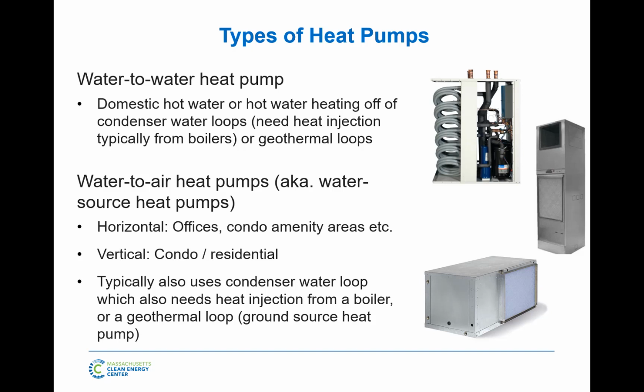Then there are the water-to-air heat pumps. That's what's commonly known as water source heat pumps. There are horizontal versions, common for office buildings and general areas, usually up in the ceiling. They go as small as a couple of tons. They can go pretty big. You can get a 10-ton water source heat pump, even larger sometimes. And then the vertical heat pumps, typically for condo buildings, maybe a third to half of the new build residential condo market, and especially mid-rise, high-rise, probably still use water source heat pumps or some version of them.